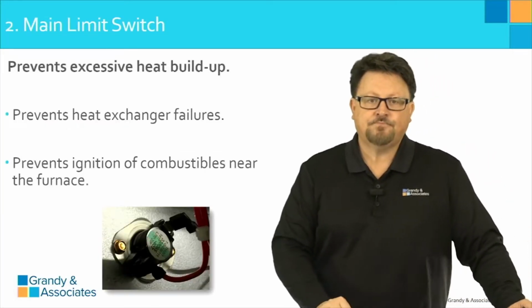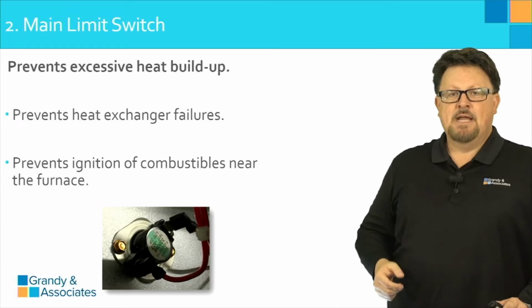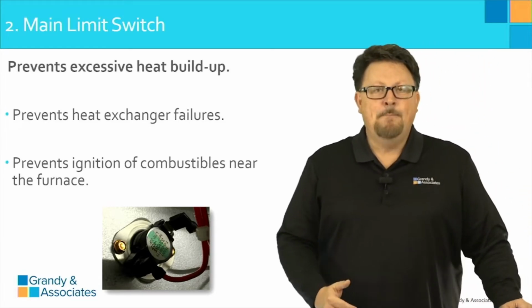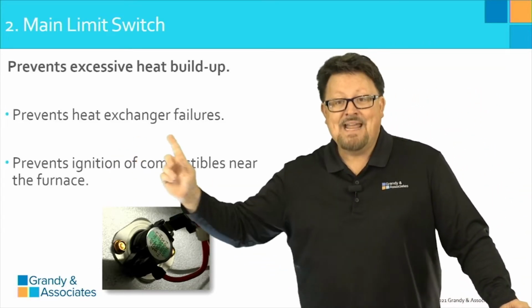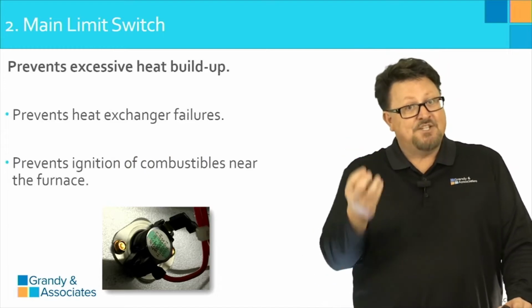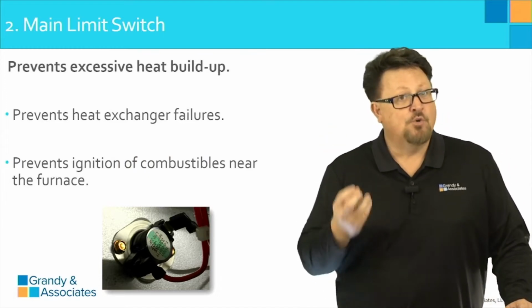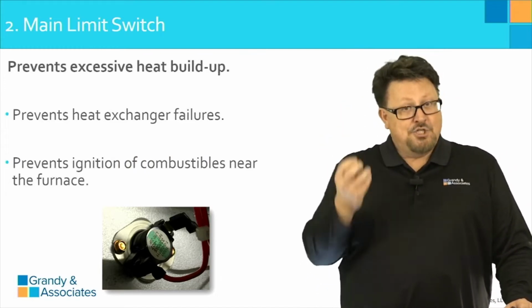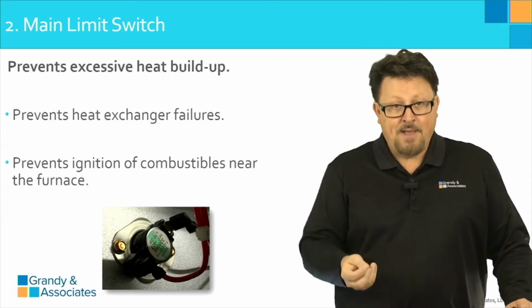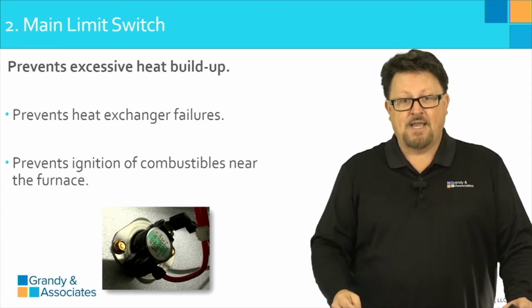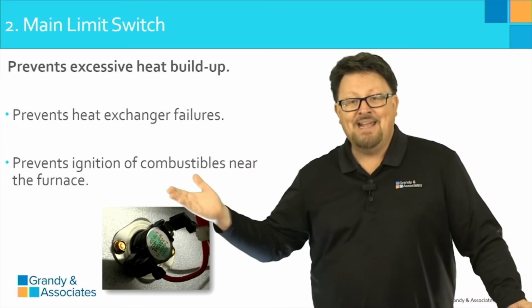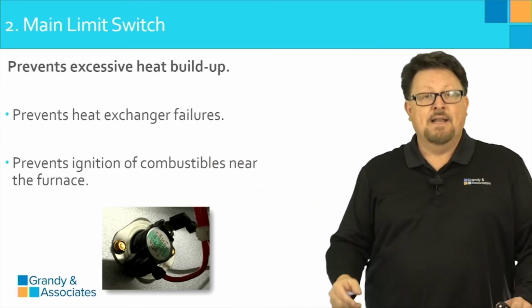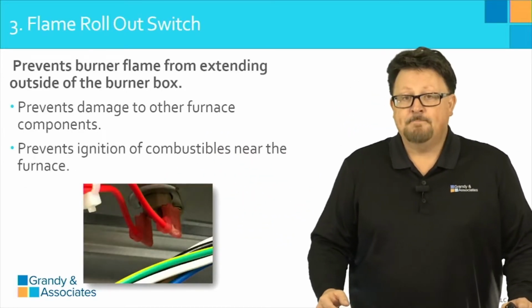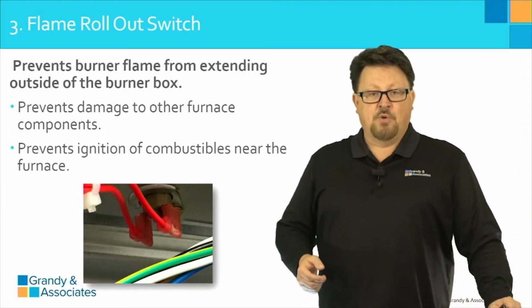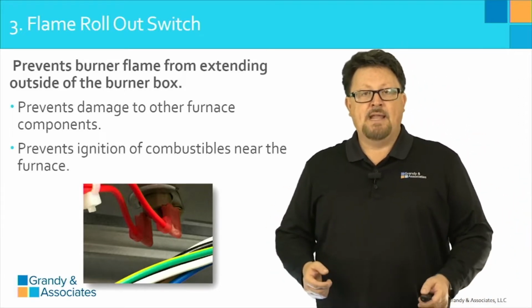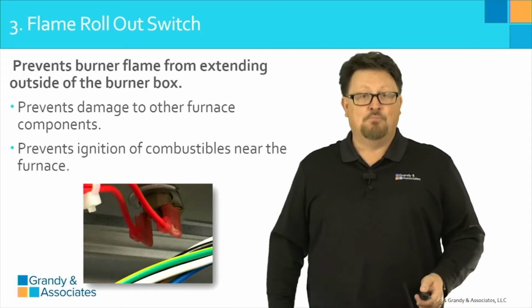Number two, main limit switches prevent excessive heat buildup, which prevents heat exchanger failures, and that's important because the heat exchanger is the workhorse of the furnace and usually the single largest repair to the furnace itself. It also helps prevent ignition of combustibles near the furnace. Number three, the flame rollout switch, which prevents the burner flame from extending outside of the burner box.